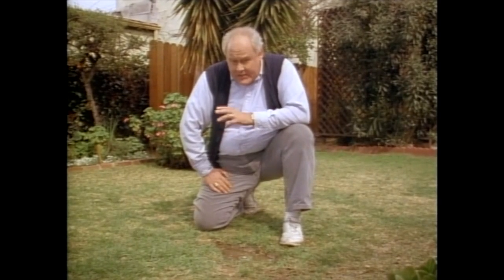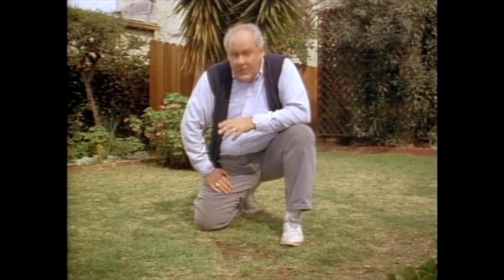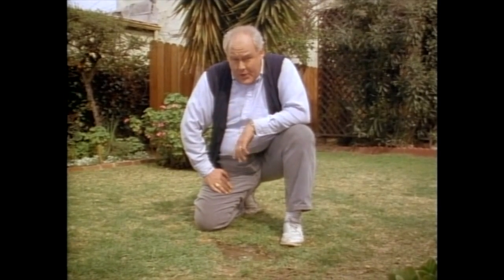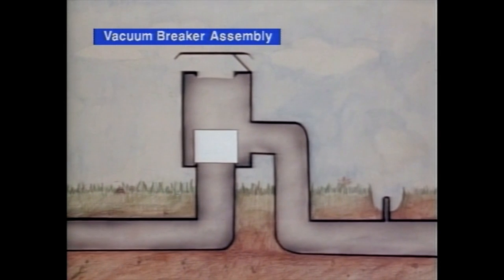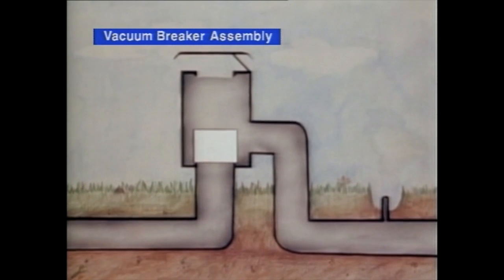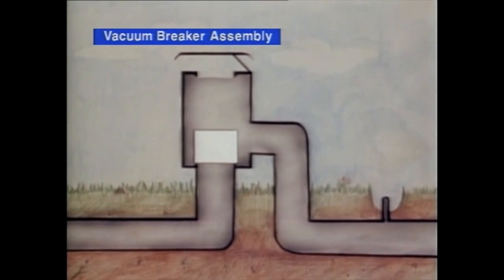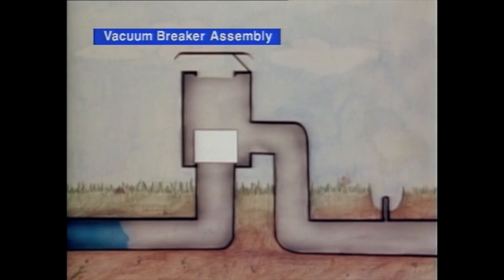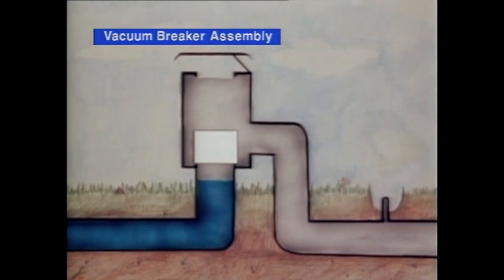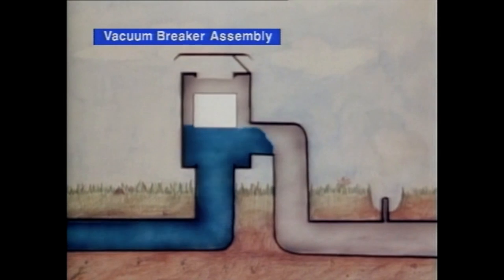Fortunately, it is easily prevented with a vacuum breaker. A vacuum breaker is basically an air vent installed in a fitting that's mounted higher than any other point downstream. There are two types of vacuum breakers: an atmospheric and a pressure vacuum breaker. Though mechanically different, they work on the same principle.